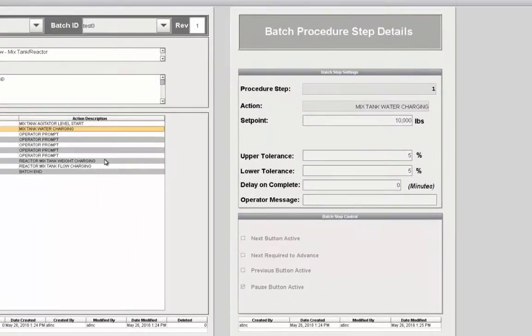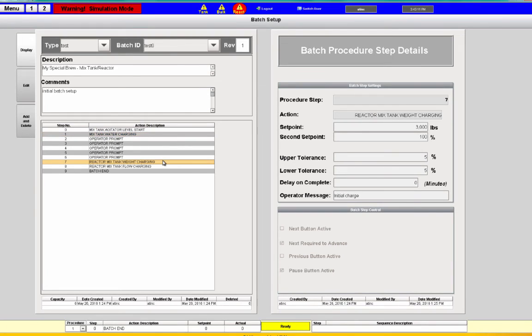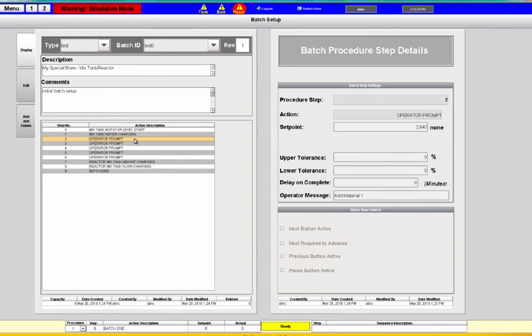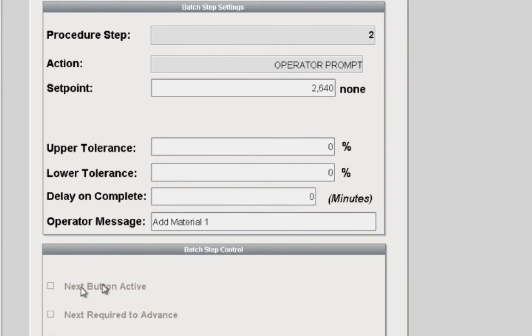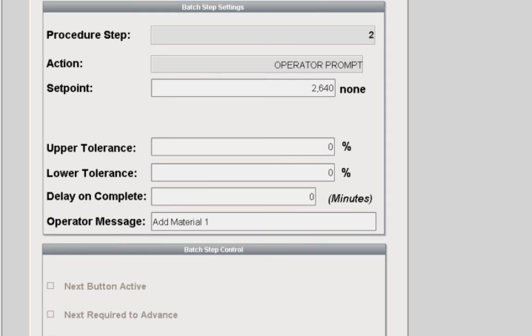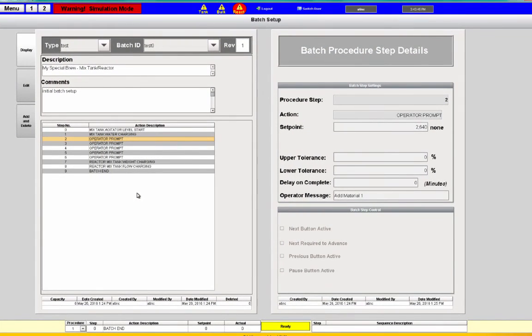'Next required to advance' is useful on certain steps where we don't want them to move on automatically. For example, looking at the reactor mixed tank weight charging, we don't want it to move straight into flow charging — we want it to pause and have the operator tell it to move on. Here are our operator prompts: we can tell the operator to add material one, tell them how much is needed, and then they'll be able to provide feedback, say that they added 2,640 as required.